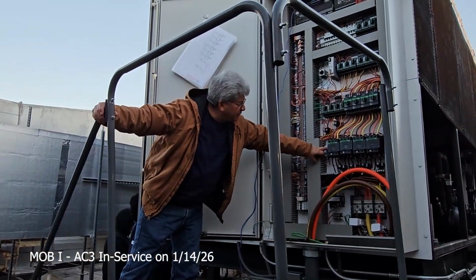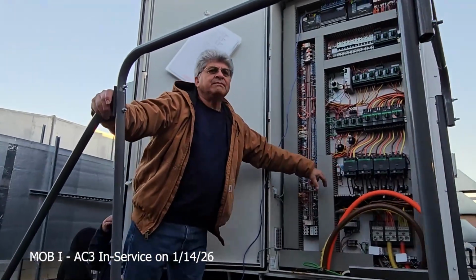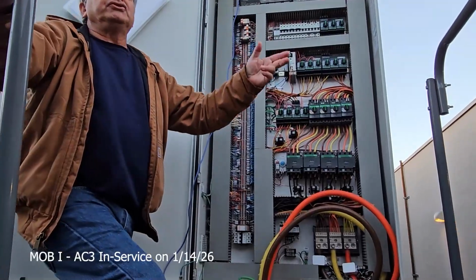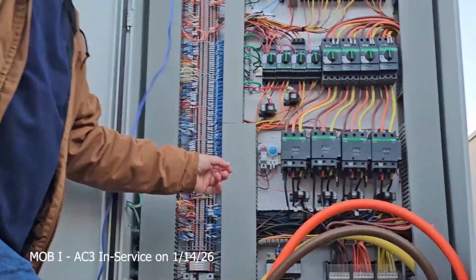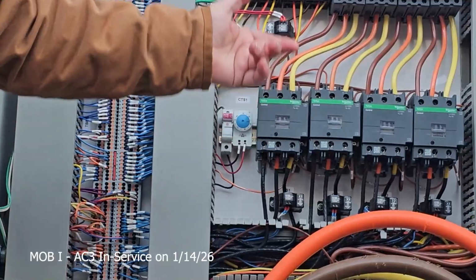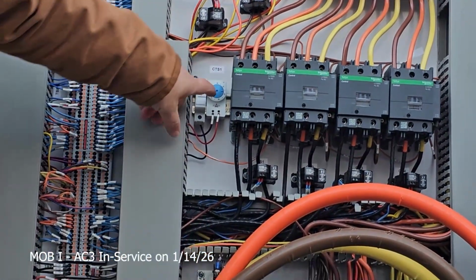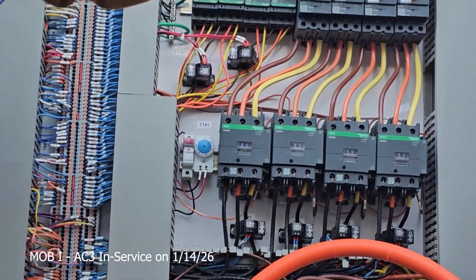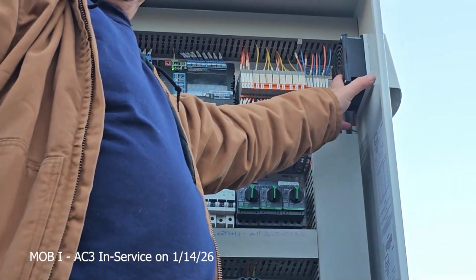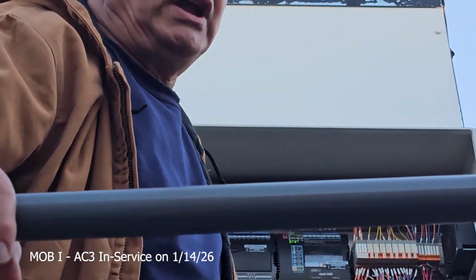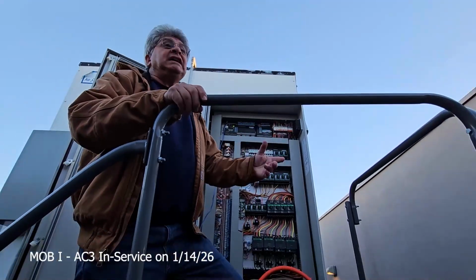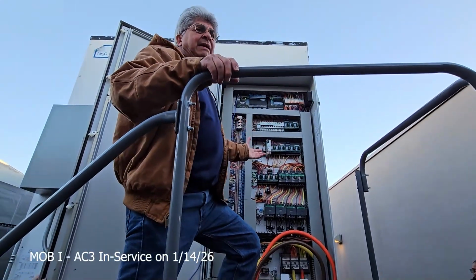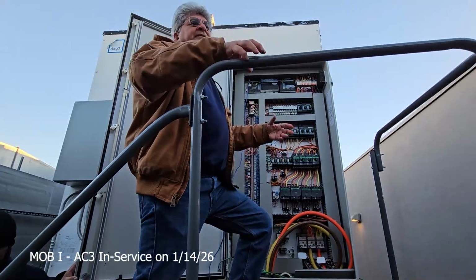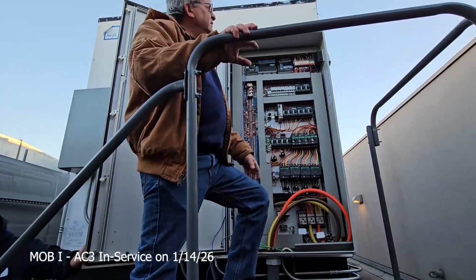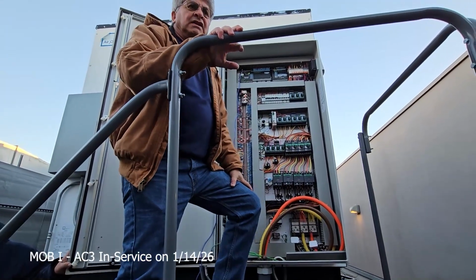This little doohickey in here, I stick my fingers in here because I'm a little older than most of you guys. Not by much, but a little bit. And I have a tremendous respect for 480 volts. This little doohickey here controls this fan. And that fan gives circulation in the cabinet, and it keeps condensation from creating inside there. You come here one day, you see condensation inside the cabinet on a hot, sticky, humid day, your fan might have stopped running. Take a look. They do burn out.